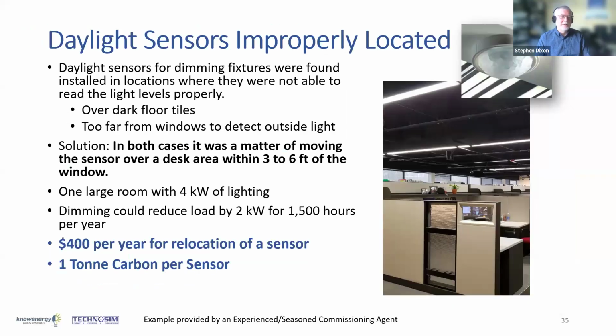Daylight sensors that are improperly located: we got the technology, but because it's over dark floors and too far away from the windows, it can't do its job to turn off the lights or modulate the lighting output. By relocating them, we got 1 ton of carbon per sensor and $400 of cost reduction.